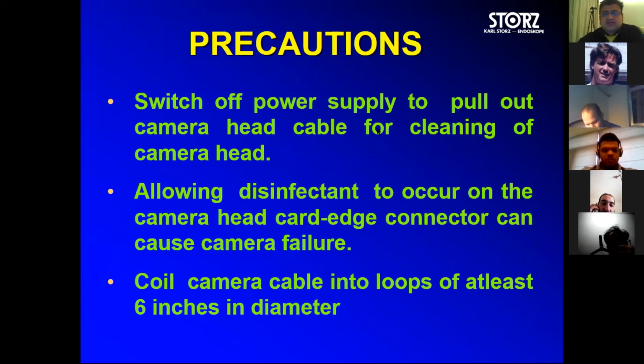Now, many times the surgeon is switching off, switching on the light source during the surgery, because sometimes you are preparing maybe a facial flap or some type of a random flap, etc. So don't do that. There is a button on the light source. You can put it onto standby mode. By continuous switching on and off, you are actually reducing the life expectancy of a xenon bulb if you are using a standard version of the xenon light source. Nowadays it is LED. The latest technology is LED 30,000 hours, and by the time you finish 30,000 hours, probably you have gone already 10-15 years ahead in your career, and something else will come.